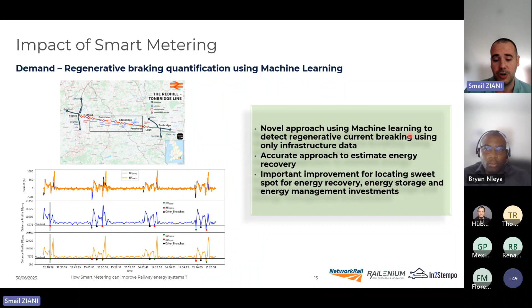The classical approach is to use the measurements of the speed and the current and the voltage from the rolling stock. Here we propose to use only the data from the substation and only the current to identify the braking energy using, of course, the patterns and some kind of machine learning approach. And like this, it's very interesting because we will have a smart approach. We use smart metering to reduce the number of measurements. And like this, it's possible to quantify very quickly and with an easy approach the energy from the regenerative braking. And like this, it's a first step, I would say, to know where it is interesting to have some energy storage like batteries in the infrastructure.